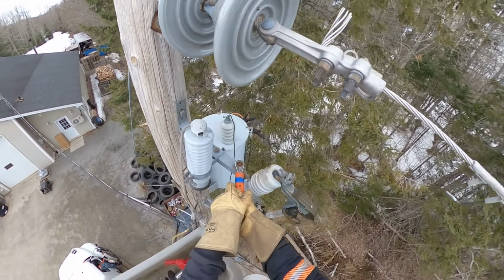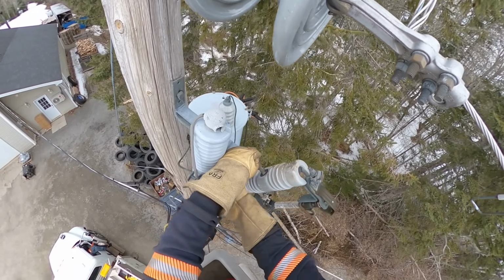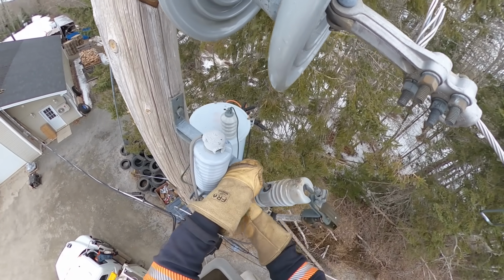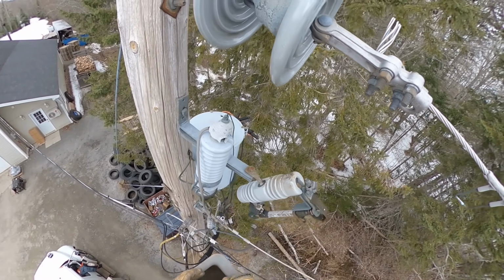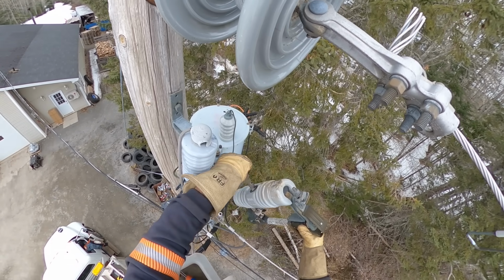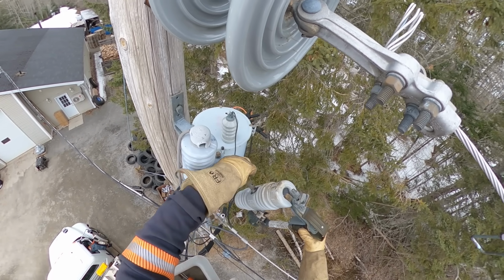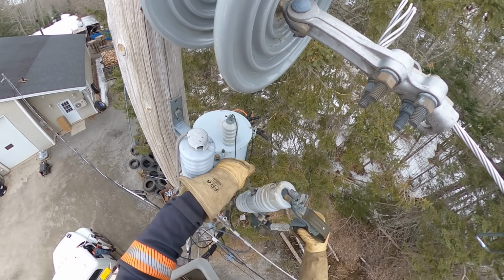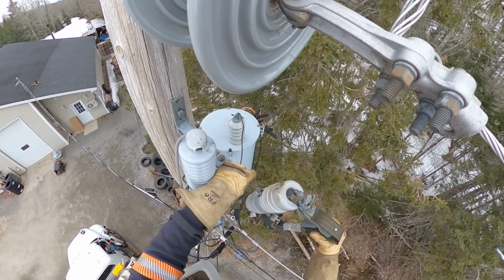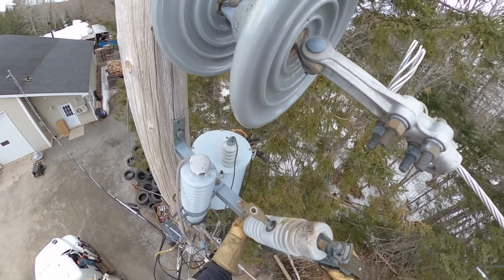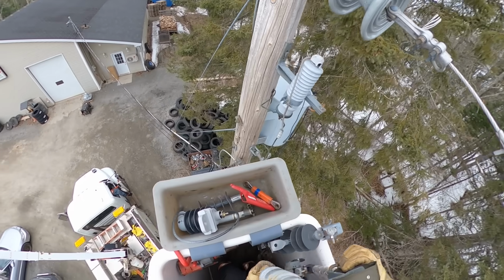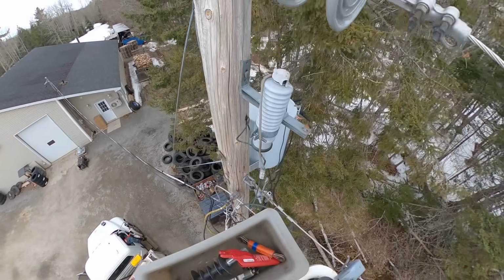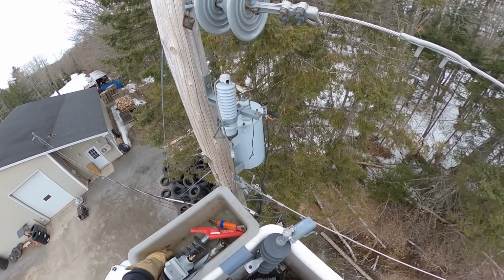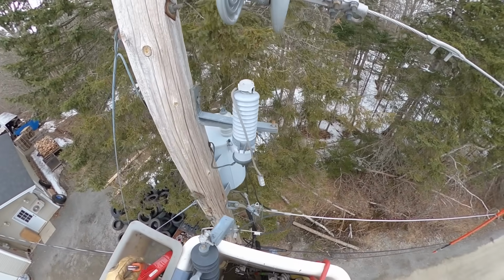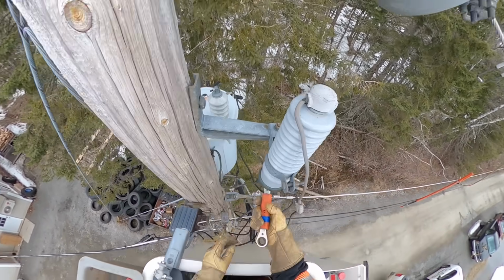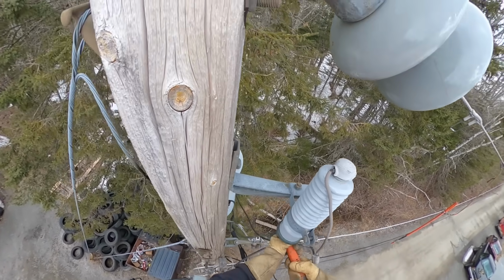Right by my left hand, that's the lightning arrestor. It's a high resistance path to ground. It's rated for a specific voltage. I think that one's 15 kV. So if the voltage, no, sorry, I'm wrong. That one's a 9 kV. So if voltage exceeds that 9 kV from, let's say, a lightning strike, that over voltage will bleed through that arrestor and into ground. Probably take out the fuse on the takeoff as well. So you can see the path to ground on the bottom. I'm just removing that.